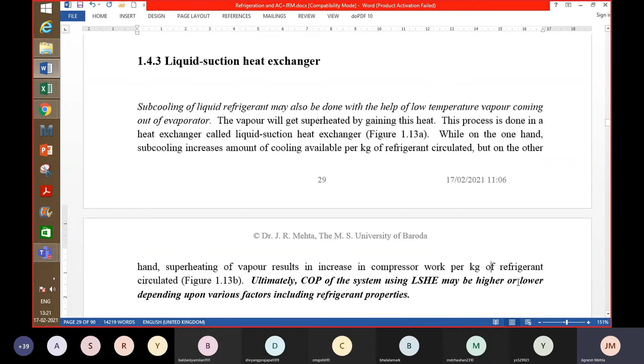Okay. Now, the other way one can achieve subcooling. In the previous case, the subcooling was achieved with some external medium, that is water. Now, you may not be using a water cooled condenser. You may be using an air cooled condenser. The other way you can achieve subcooling is by superheating the vapor coming out of the evaporator.